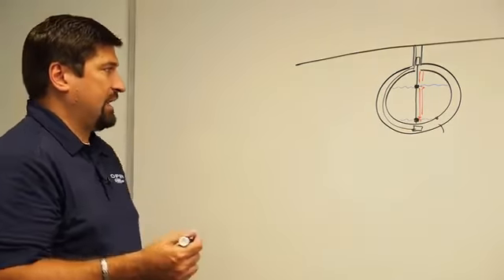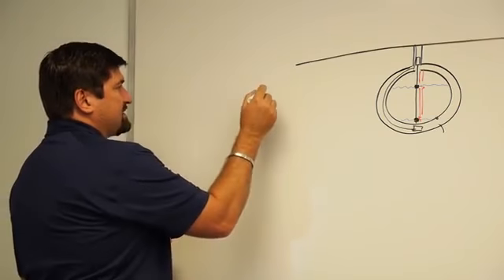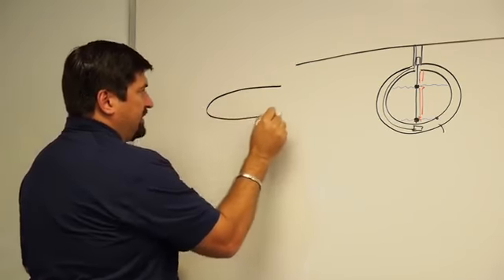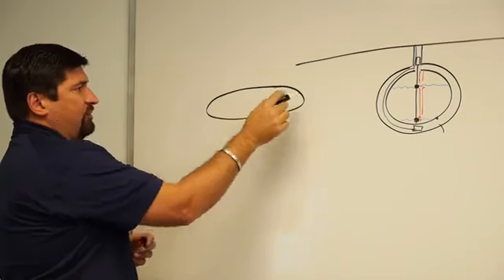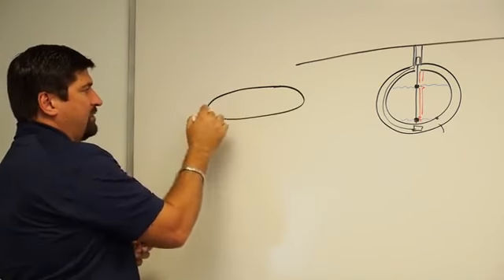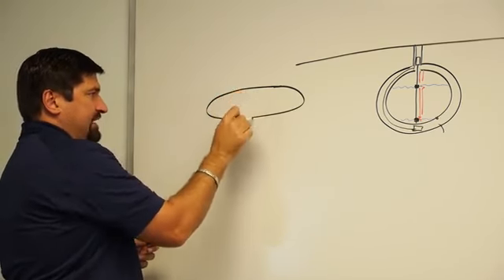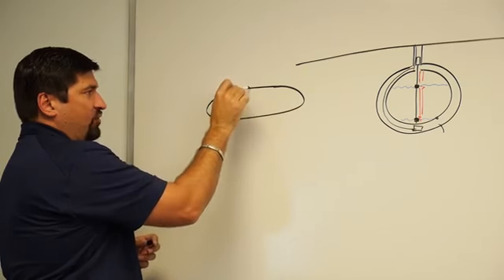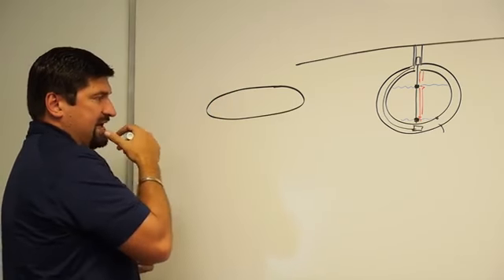Now this is a fiberglass tank. Now in a fiberglass tank, you're looking at the shape, and a fiberglass tank will normally be cylindrical with round ends. And then you're able to put that sensor in at the bottom of the tank through one of the ribs that go along the outer side.